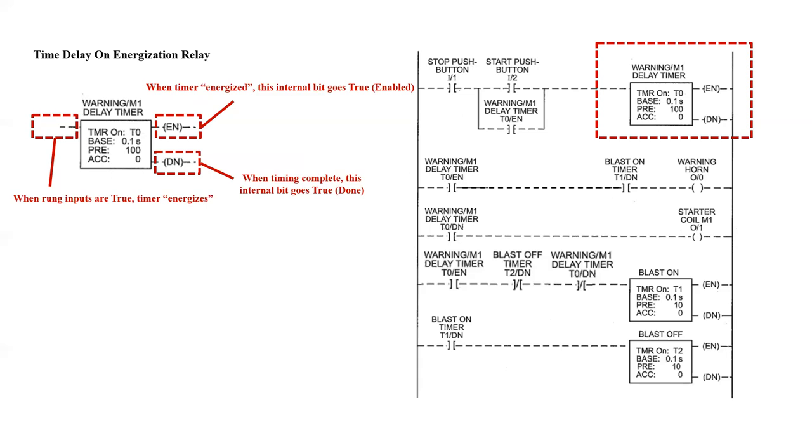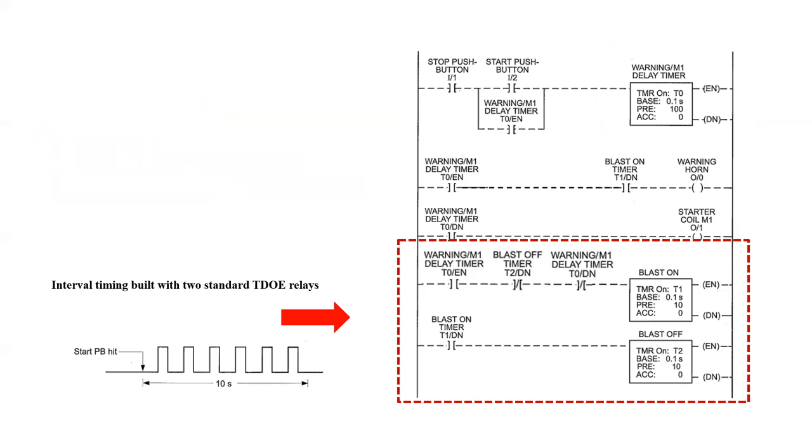When the input rung is true, the timer will be energized, and as soon as it's energized, it will start to time. At the bottom, we have a large section of the PLC program whose sole purpose is to provide an interval timing setup where the horn will be off for one second, on for one second, off for one second, on for one second, and that will be through the flip-flopping use of two separate time delay on energization timers.